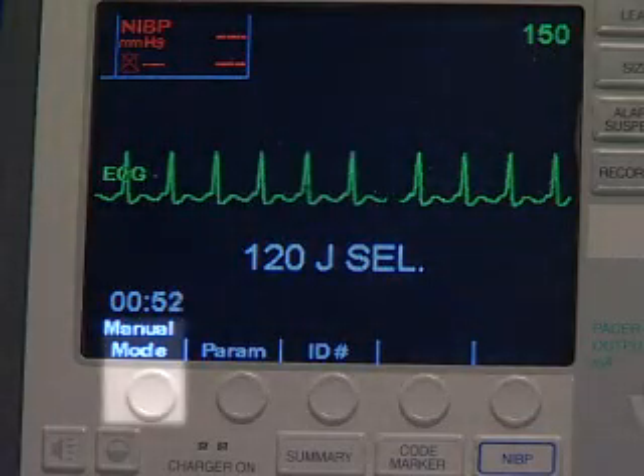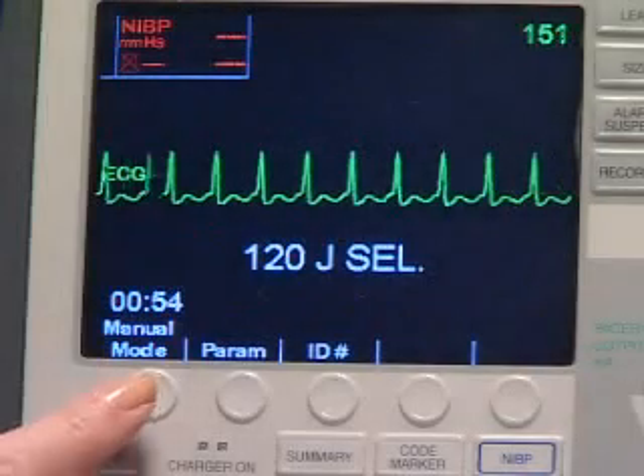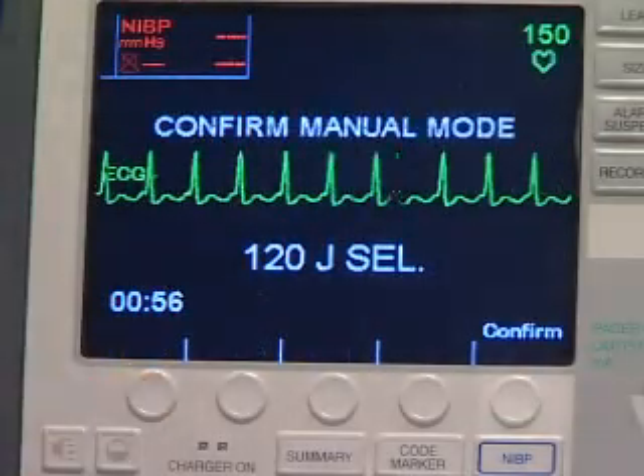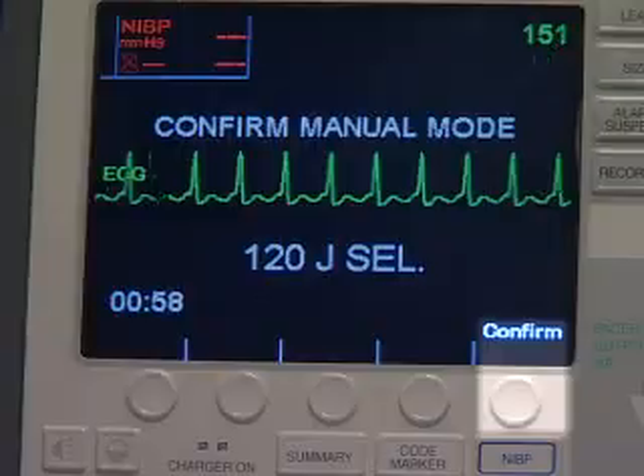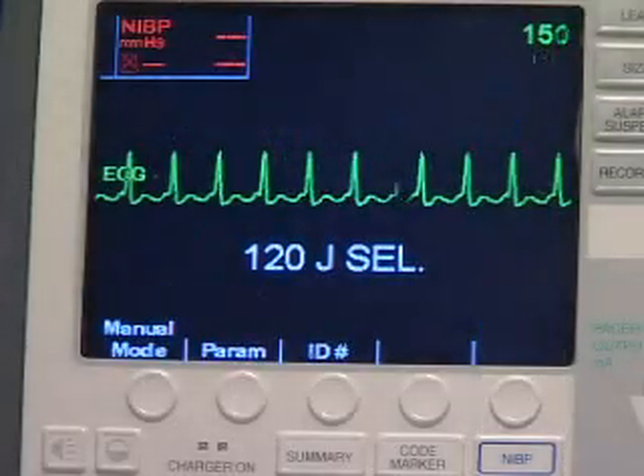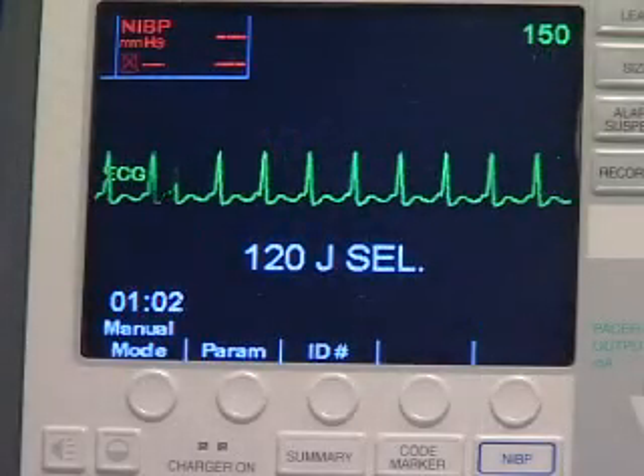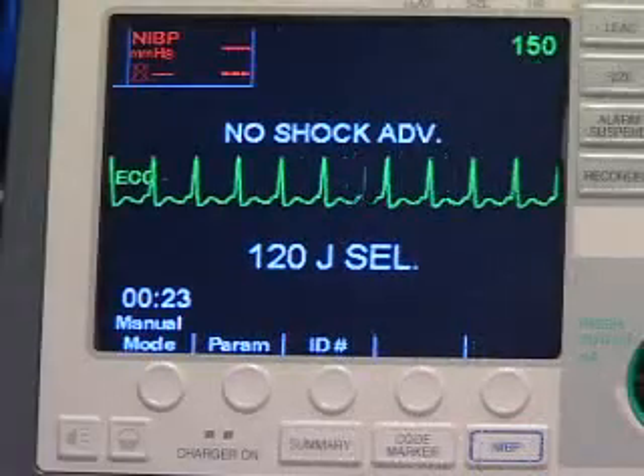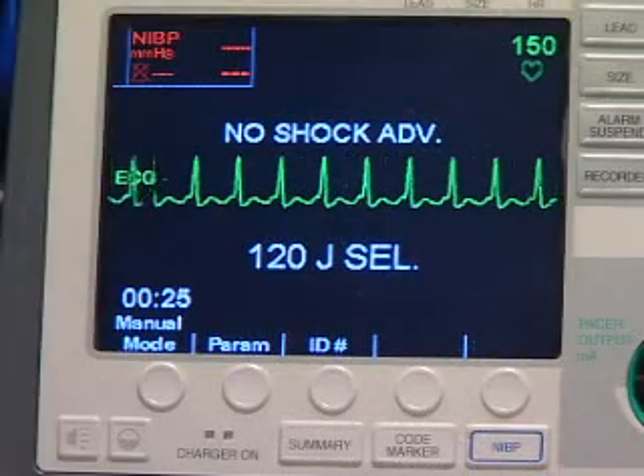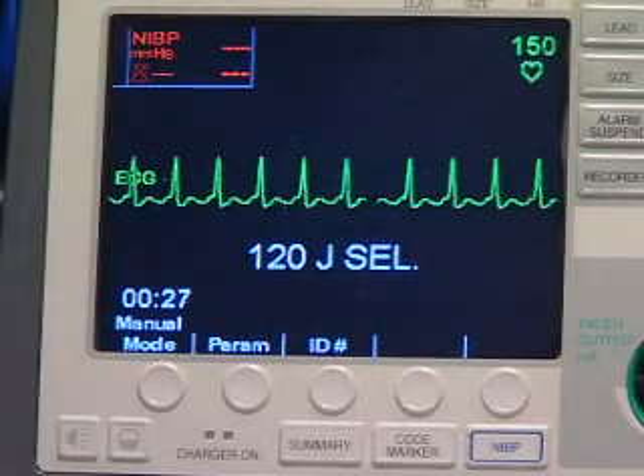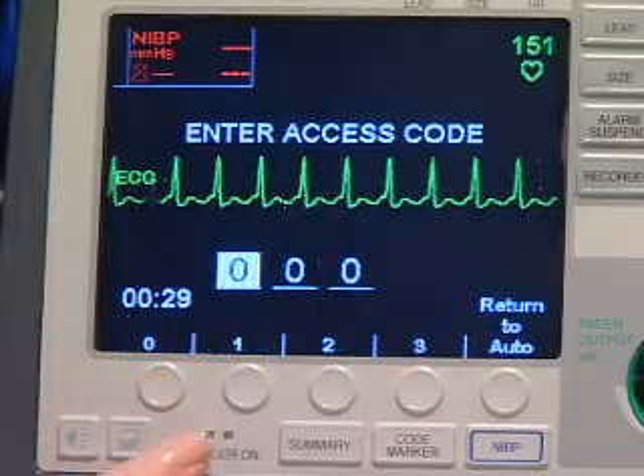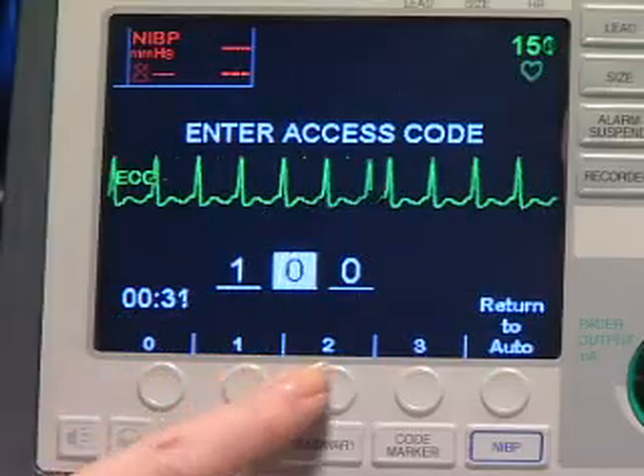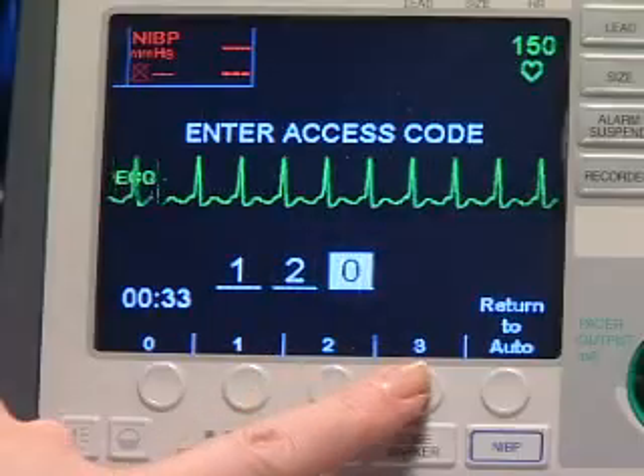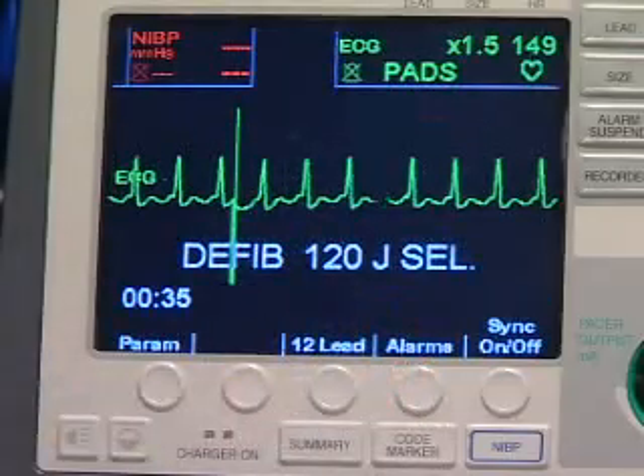Press the manual mode soft key on the front panel of the E-Series to enter the manual mode of operation. If the confirm soft key is not pressed within 5 seconds, the unit will revert to semi-automatic operation. If your E-Series has been configured to require an access code, enter access code will be displayed. You need to enter a 3-digit access code by pressing the soft keys corresponding to the correct digits.